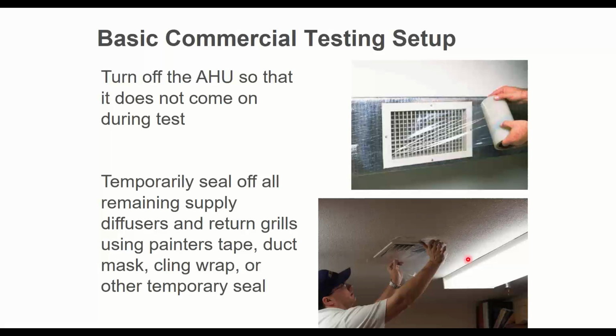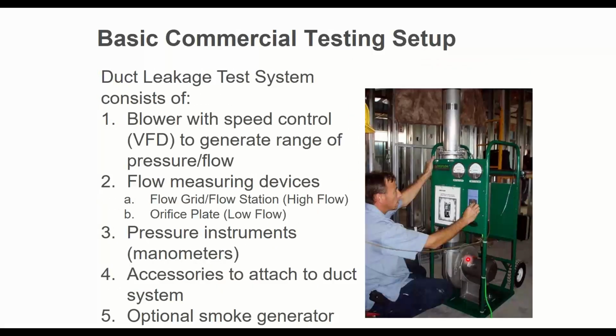If I close off all the diffusers, and then I make a hole in the duct, and I run this fan to inject air into it, if I am able to move air into that duct system, that means air is moving out of the duct system somewhere. And if I can measure how much air I shove into the duct, I will then know how much air is coming out of the duct. Because it'd be very hard to measure all the little tiny gaps and leaks. Like you have to go around the building somehow and quantify them. But we don't have to do that. If I inject all the air in that one singular point, I can just measure how much air I'm injecting in. And that is, in fact, how much air I am leaking out.